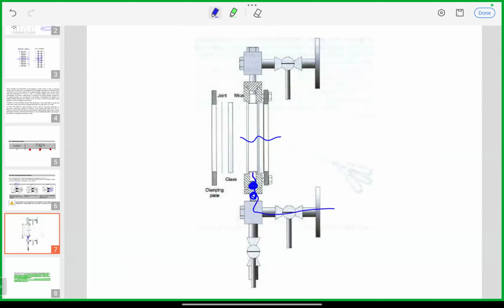What will happen if water starts to come out? The water already inside the boiler is under pressure and at high temperature. So when that water at that temperature is suddenly exposed from high pressure to atmospheric pressure, the boiling point is going to decrease drastically. So the water will start to convert into steam and flash up, occupying a large volume of the engine room.